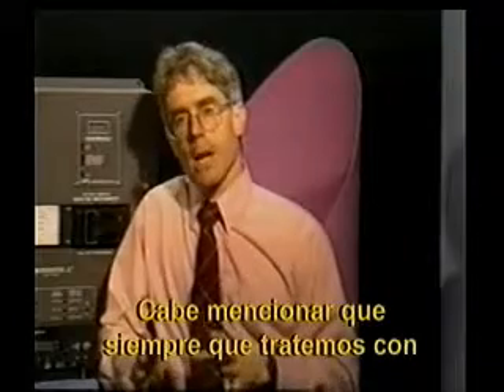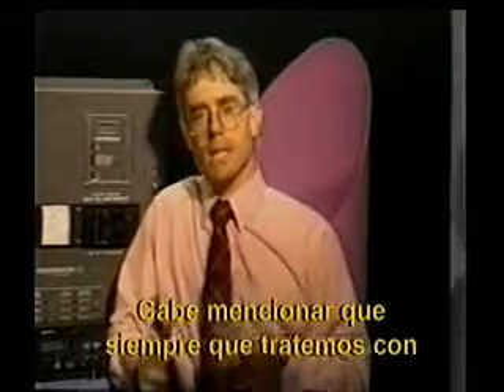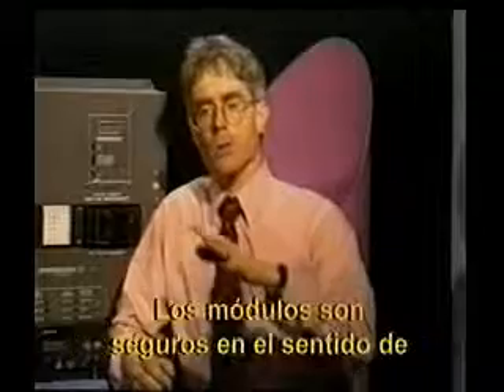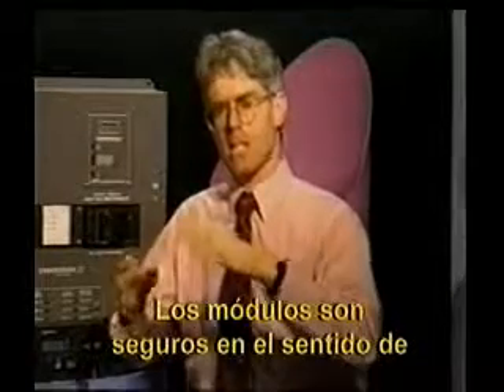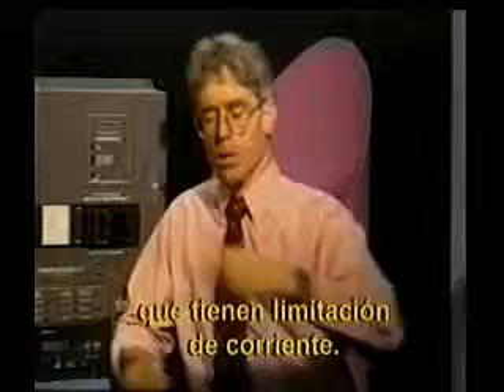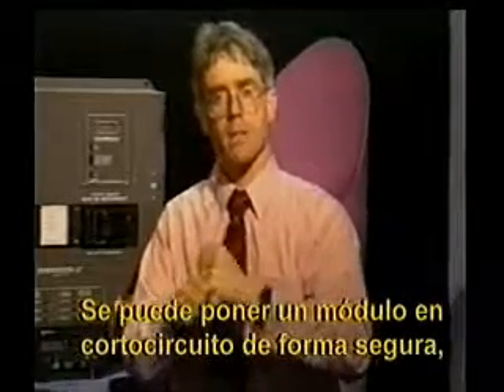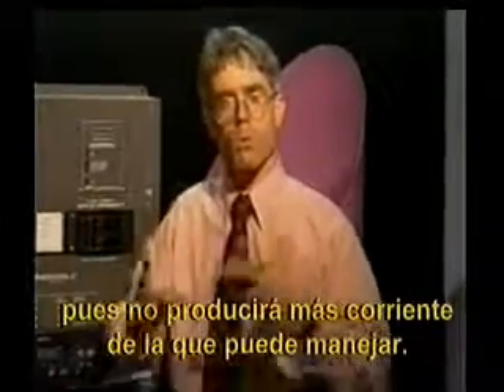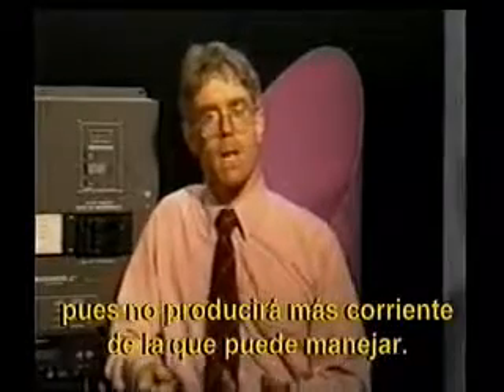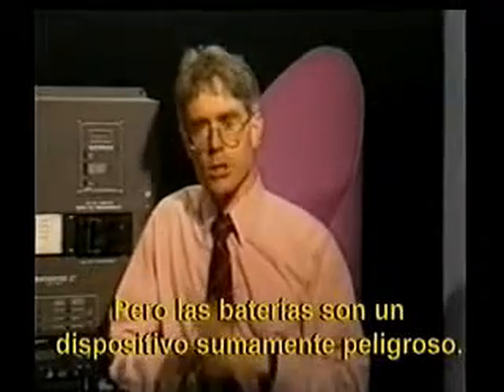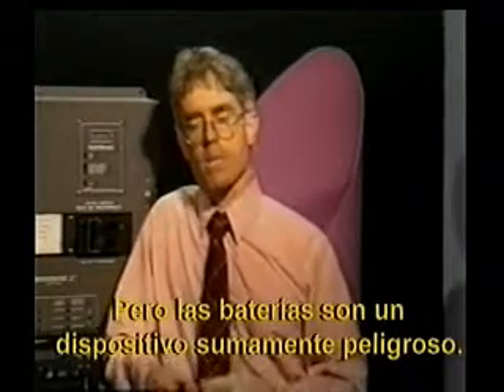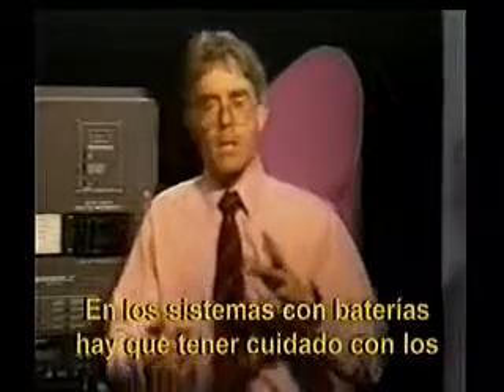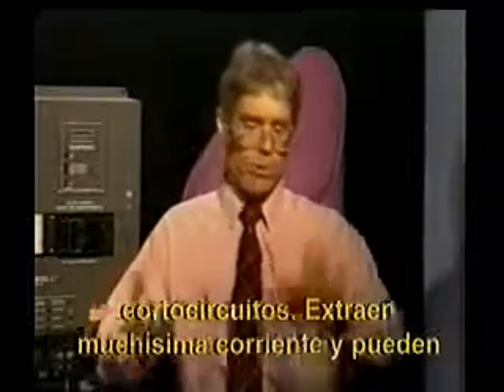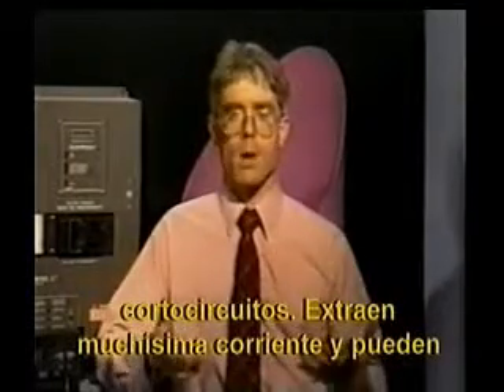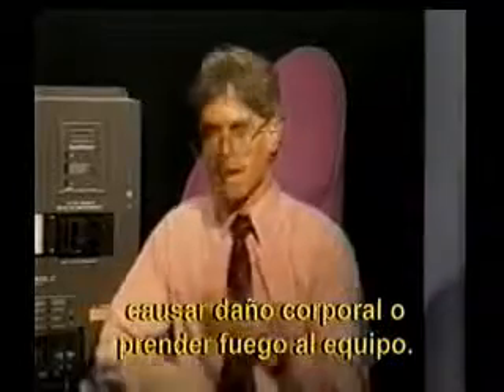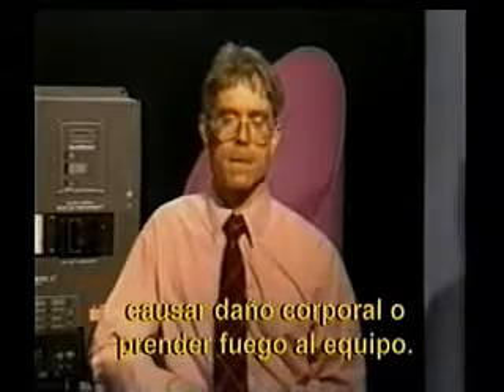One note that we should talk about here, when we're dealing with batteries, we're dealing with danger. Modules are fundamentally safe in the sense that they're current limited. You can short circuit a module safely. It won't run away in current. It won't produce more current than it can handle. But with batteries, you're dealing with an extremely dangerous device. We have to be concerned about short circuits in systems with batteries, drawing tremendous amounts of current, perhaps causing bodily harm or at least dangerous damage, perhaps fires to our equipment.